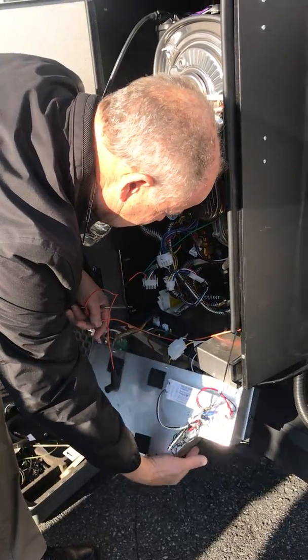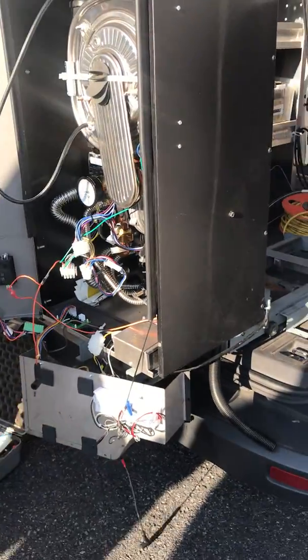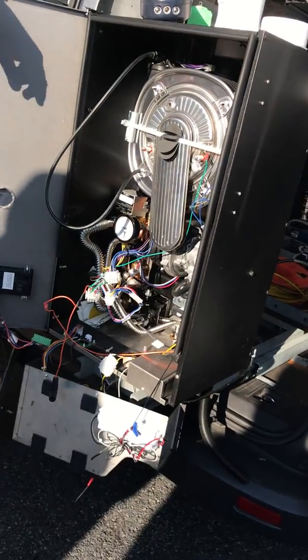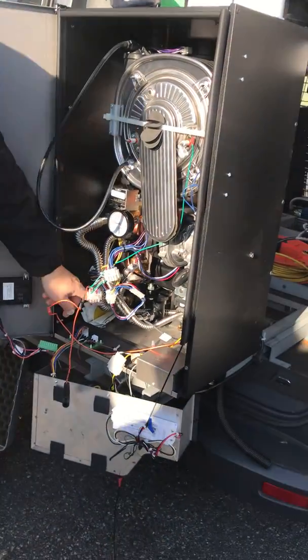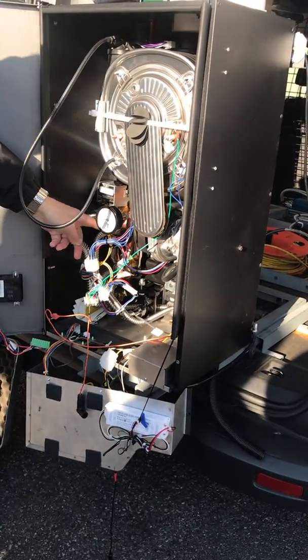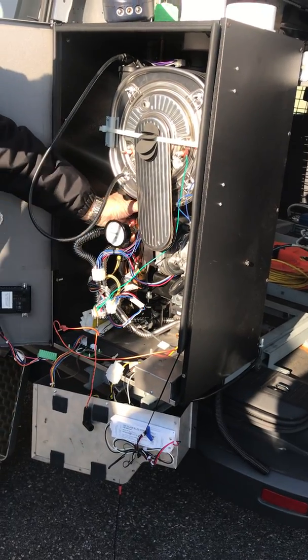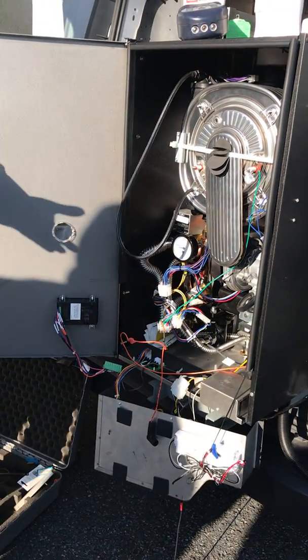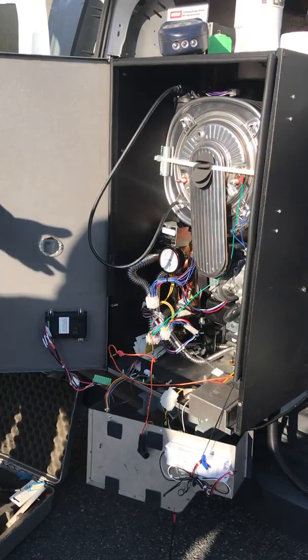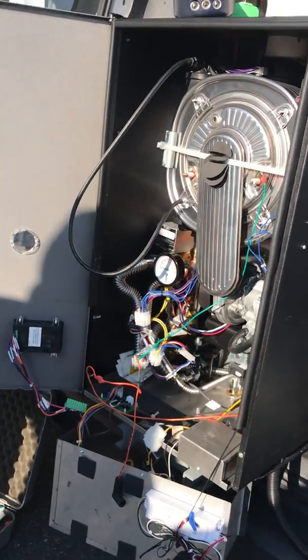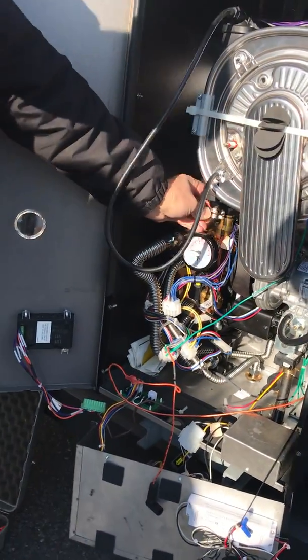So I can get this out of the way. So this whole thing can be pulled out. Now my circulator's in through there. Here's the other thing. If you ever had a problem with a heat exchanger, all that holds the heat exchanger is some clips and there's some screws. So the heat exchanger, and there's an O-ring.